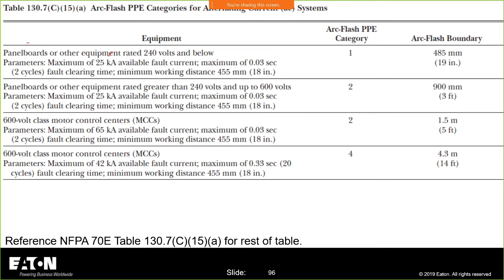We know there's notes to this table that tell you a molded case circuit breaker is going to clear in 2 cycles. An insulated case circuit breaker is going to take more than 2 cycles. A power circuit breaker could take up to 30 cycles, right? So by looking at this, as long as I'm seeing a 2-cycle clearing time, I know I'm downstream of a molded case circuit breaker.